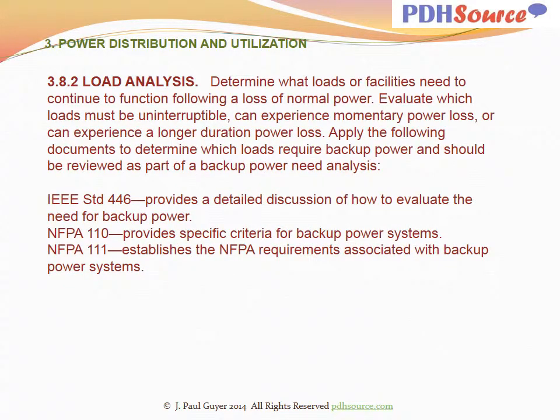Load analysis. Determine what loads or facilities need to continue to function following a loss of normal power. Evaluate which loads must be uninterruptible, can experience momentary power loss, or can experience a longer duration power loss. Apply the following documents to determine which loads require backup power and should be reviewed as part of a backup power needs analysis. IEEE Standard 446 provides a detailed discussion of how to evaluate the need for backup power. NFPA 110 provides specific criteria for backup power systems. NFPA 111 establishes the NFPA requirements associated with backup power systems.